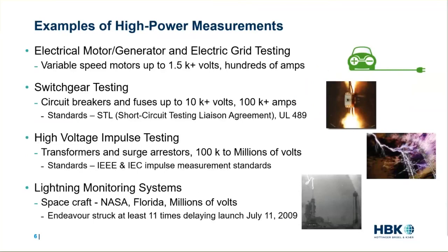There's switchgear testing, circuit breakers and fuses up to maybe 10K volts, 100K amps. Standards include STL, the Short Circuit Testing Liaison Agreement, and UL 489, we'll talk more about that. High voltage impulse testing, transformers and surge arresters, dealing with 100K to millions of volts, basically simulating lightning. Standards include the IEEE and IEC impulse measurement standards.